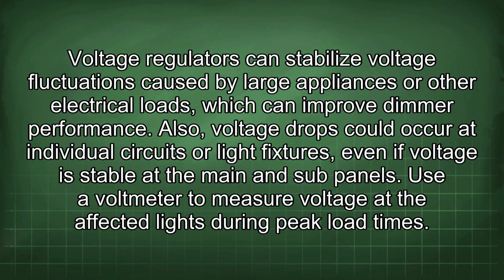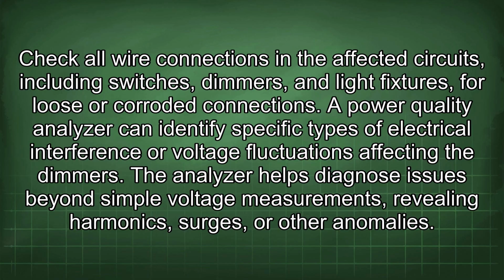Voltage regulators can stabilize voltage fluctuations caused by large appliances or other electrical loads, which can improve dimmer performance. Also, voltage drops could occur at individual circuits or light fixtures, even if voltage is stable at the main and sub-panels. Use a voltmeter to measure voltage of the affected lights during peak load times. Check all wire connections in the affected circuits, including switches, dimmers, and light fixtures, for loose or corroded connections.